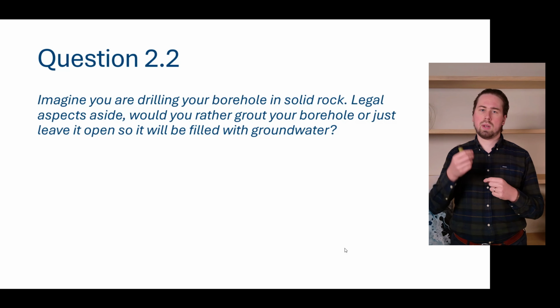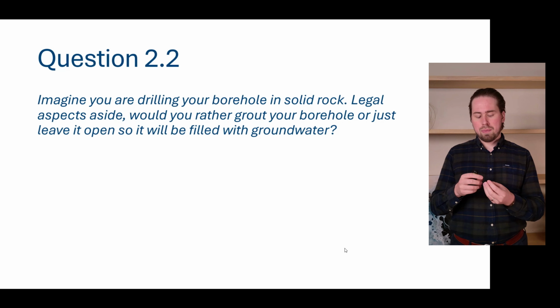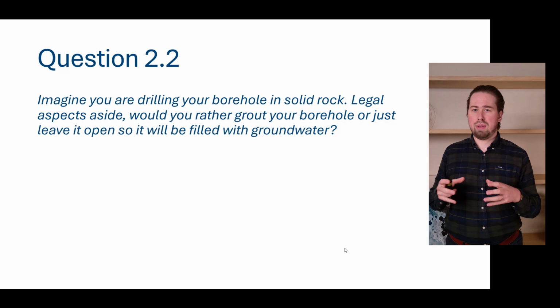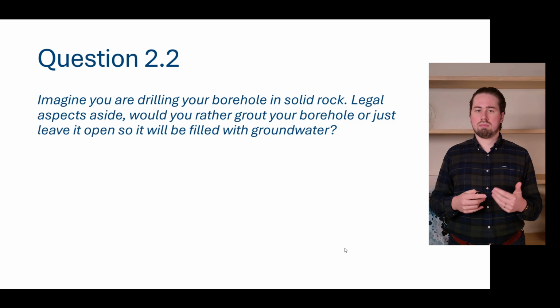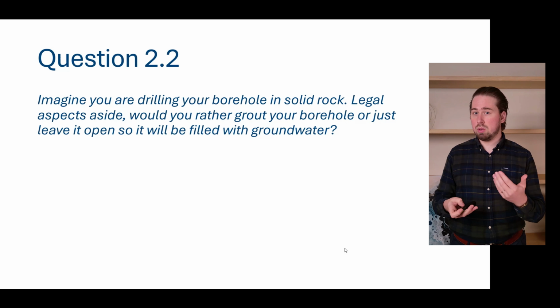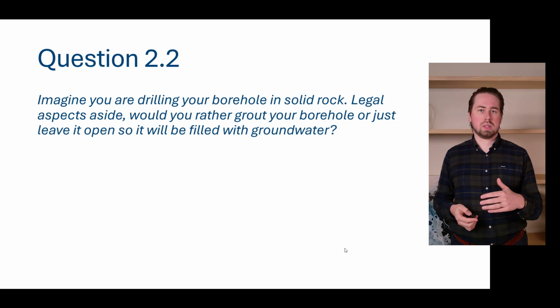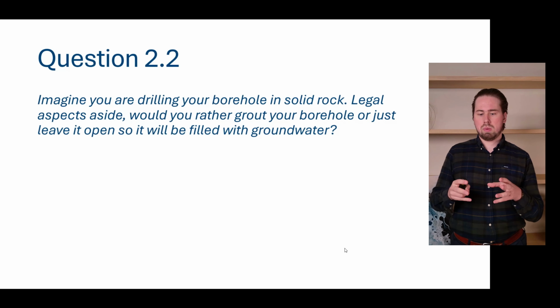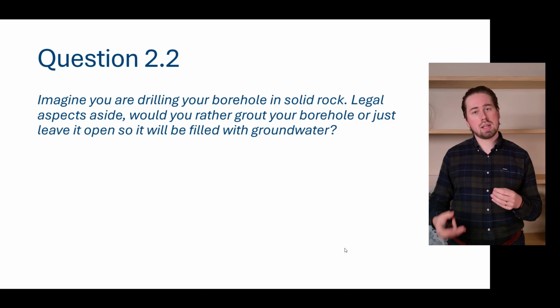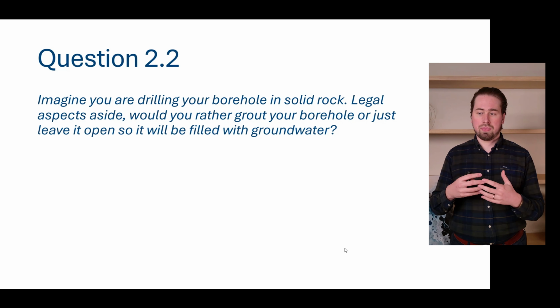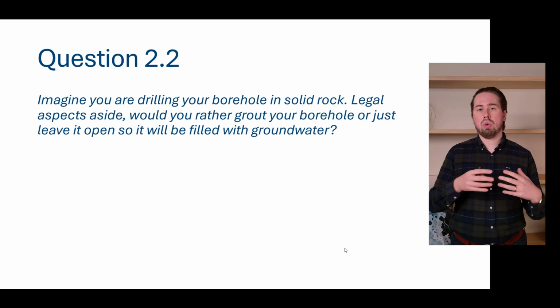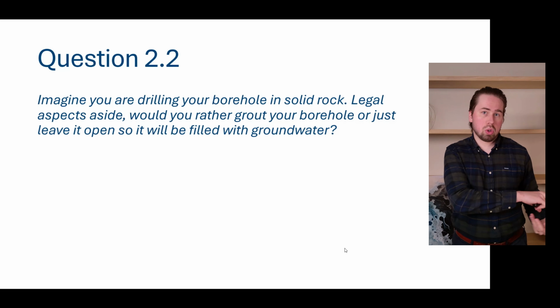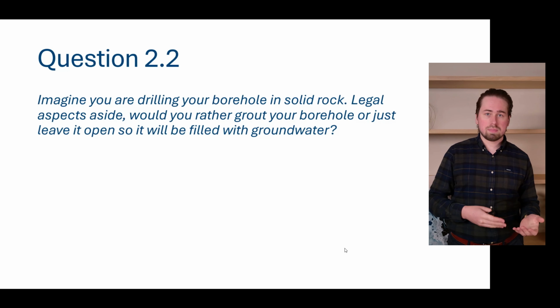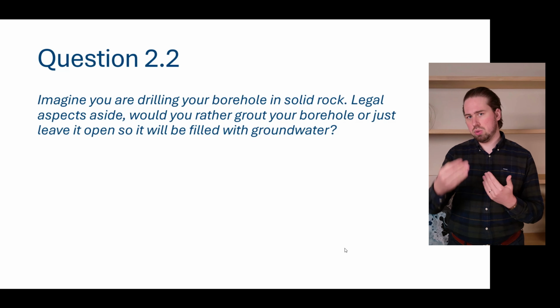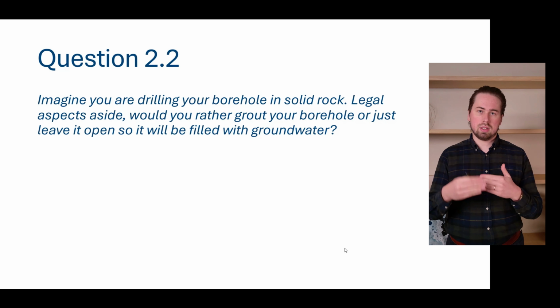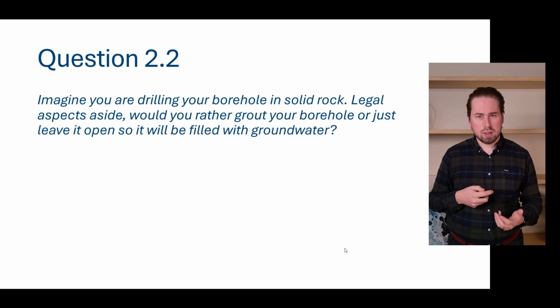Now the situation changes a little bit when you go to negative temperatures, because then the fluid starts freezing and this buoyancy effect goes away. And you will end up with the conductivity of static water, which is actually worse than what you would have had if your borehole was actually grouted. So here there is a trade-off. Would I drill more in this case, in order to make sure that the temperatures are good, or that we have enough borehole length to work with this worse effective borehole thermal resistance? Or should I grout my borehole to make sure that if we go to really cold temperatures we still have this good thermal conductivity in the borehole? So that's a design question.